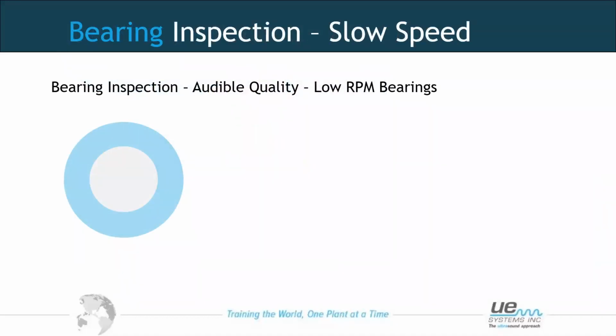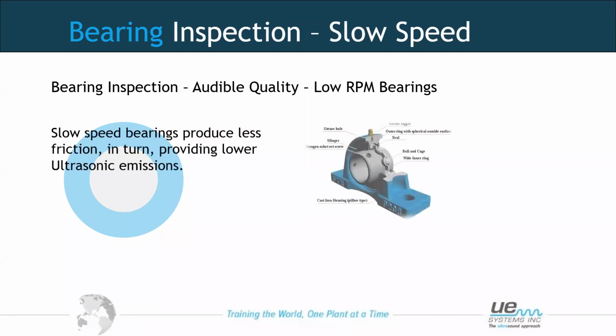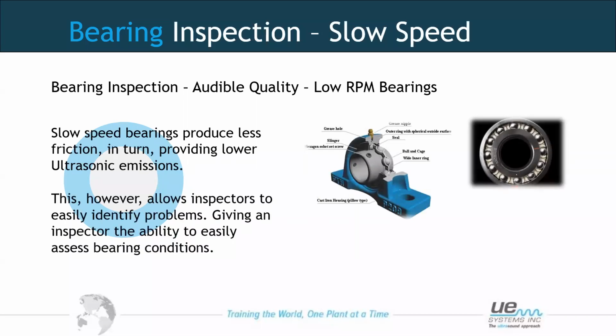So going on to slow speed applications, this is an area where ultrasound really does have a good benefit with predictive technologies. Because again, even at slow speed, we're generating friction, so we're generating ultrasound. Okay, so we can actually still diagnose and listen to the condition of our bearings. So at slow speed, we're going to produce less friction, but it will still produce ultrasound at just a lower emission. So this helps us with identifying the condition.